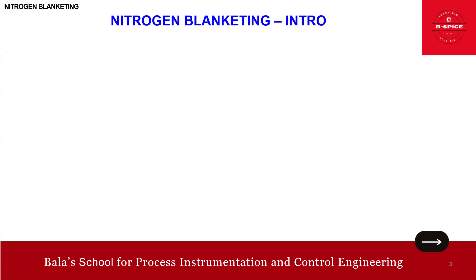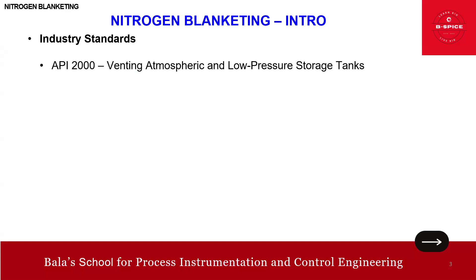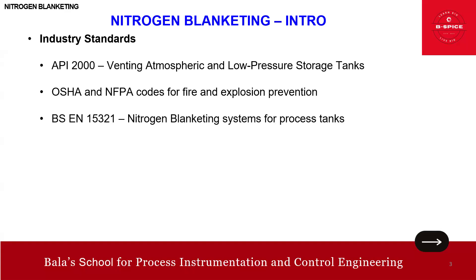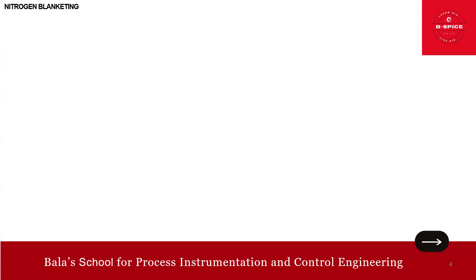Now we'll look at the industry standards. API 2000 relates to venting of atmospheric and low-pressure storage tanks. OSHA and NFPA cover fire and explosion prevention. In BSpice, we've also uploaded three videos on instrumentation codes and standards covering everything from A to Z. Additionally, BS EN 15321 is related to nitrogen blanketing systems for process tanks. These are the key standards relevant to this subject.